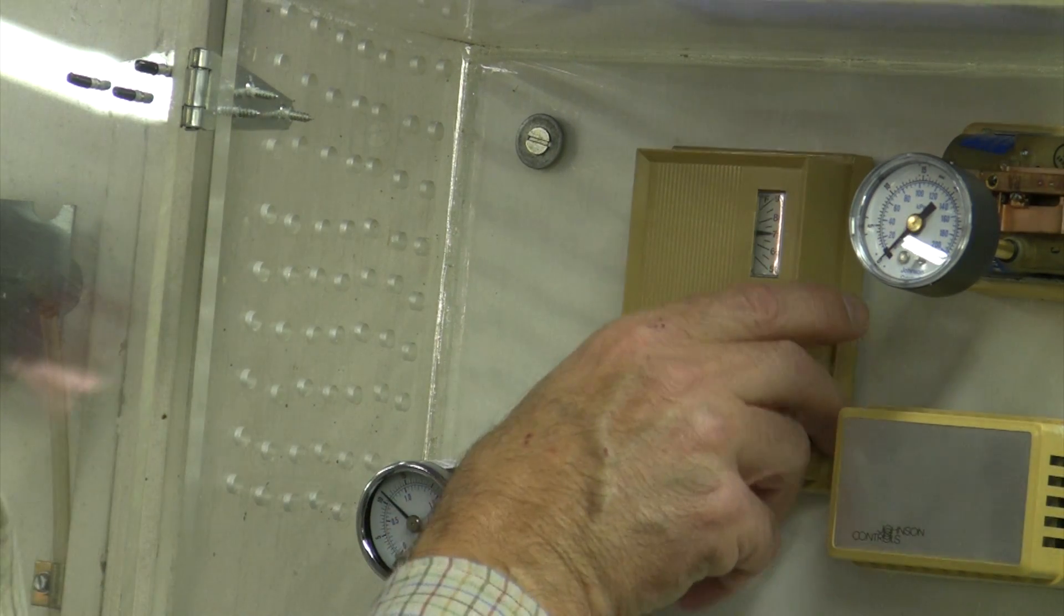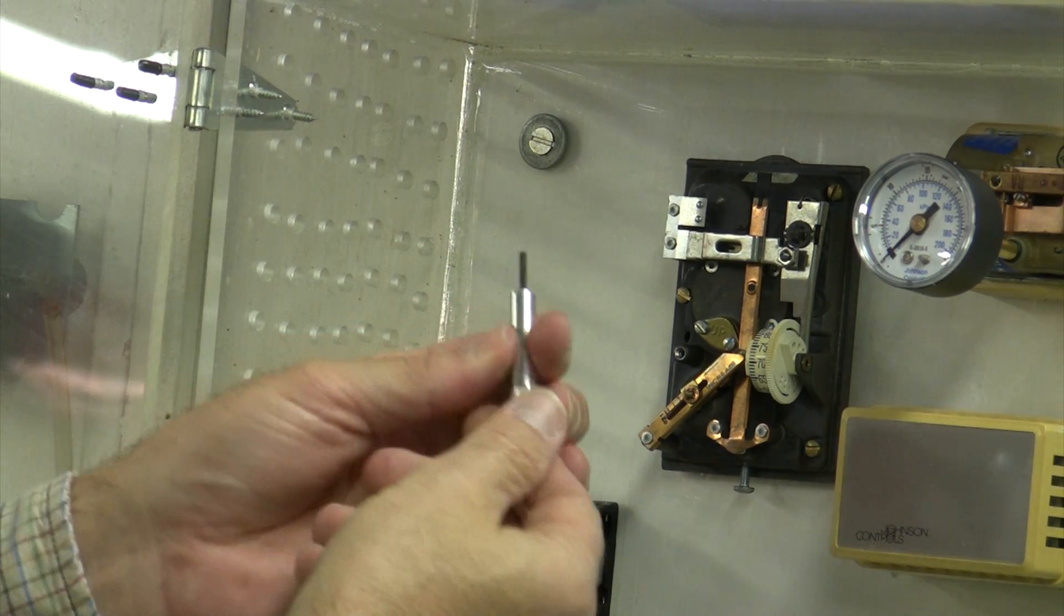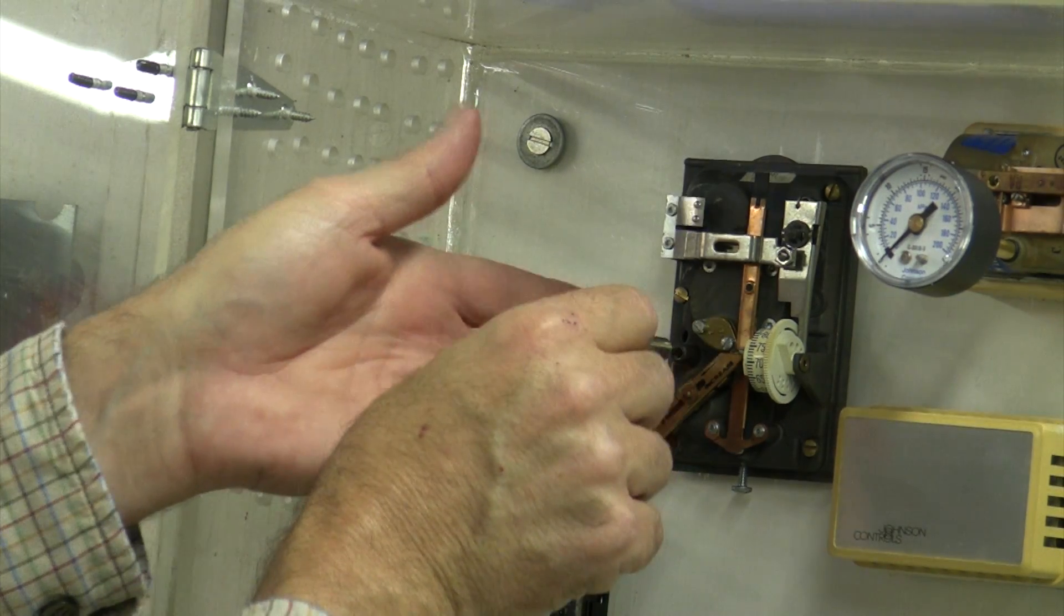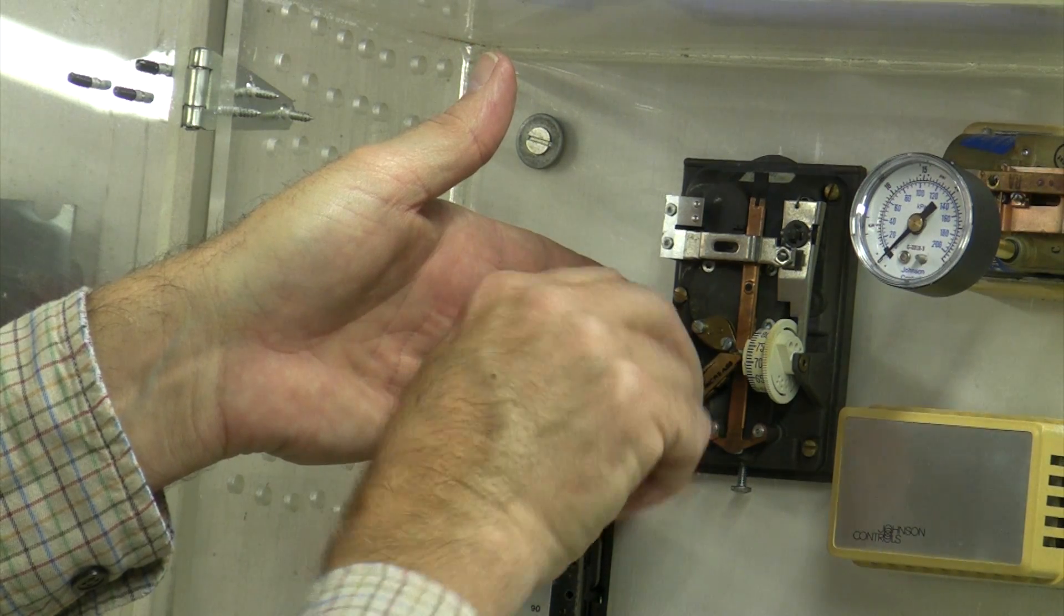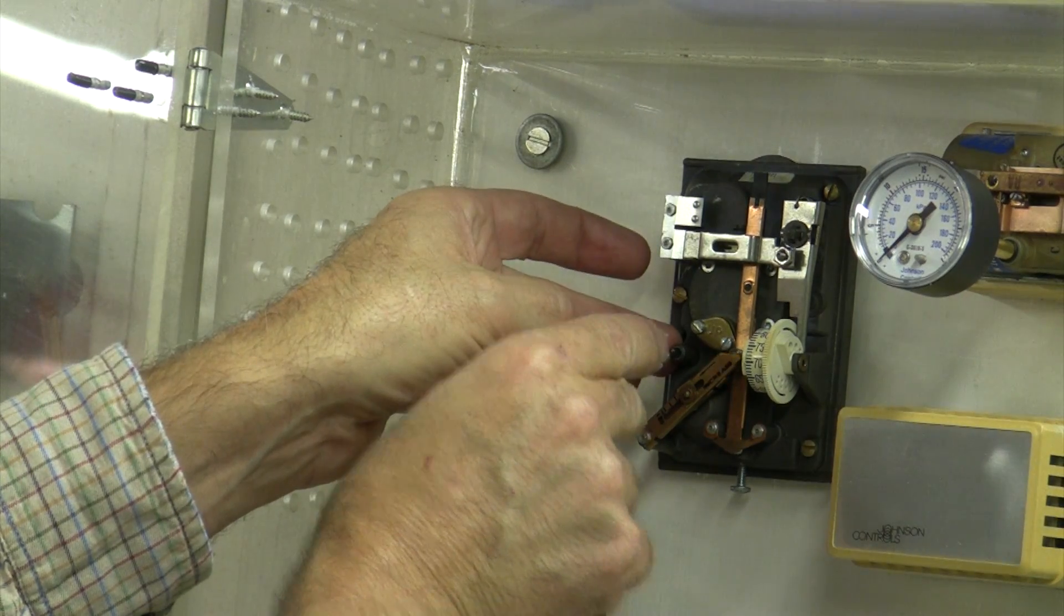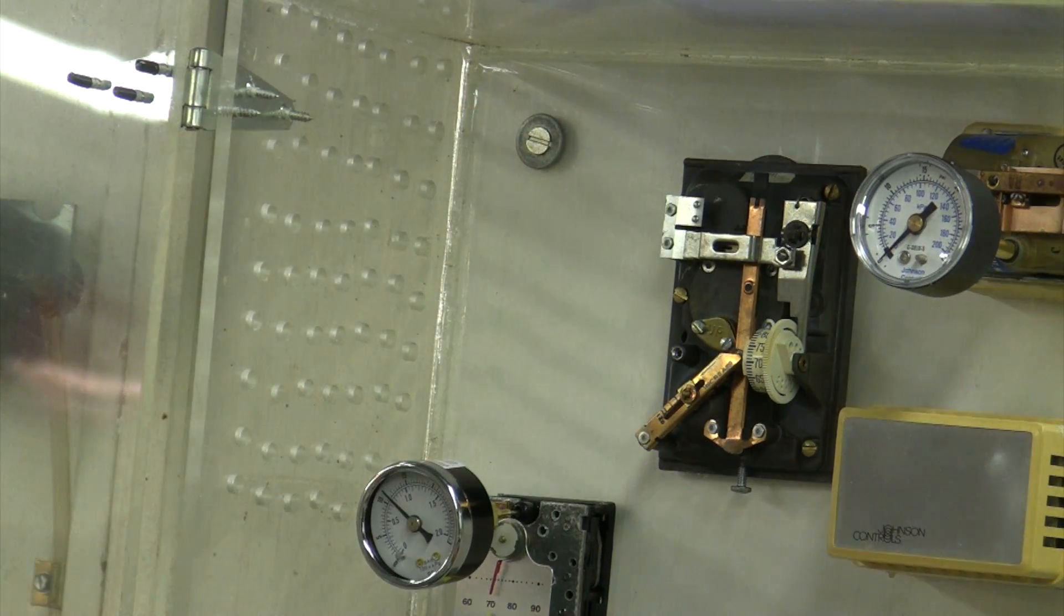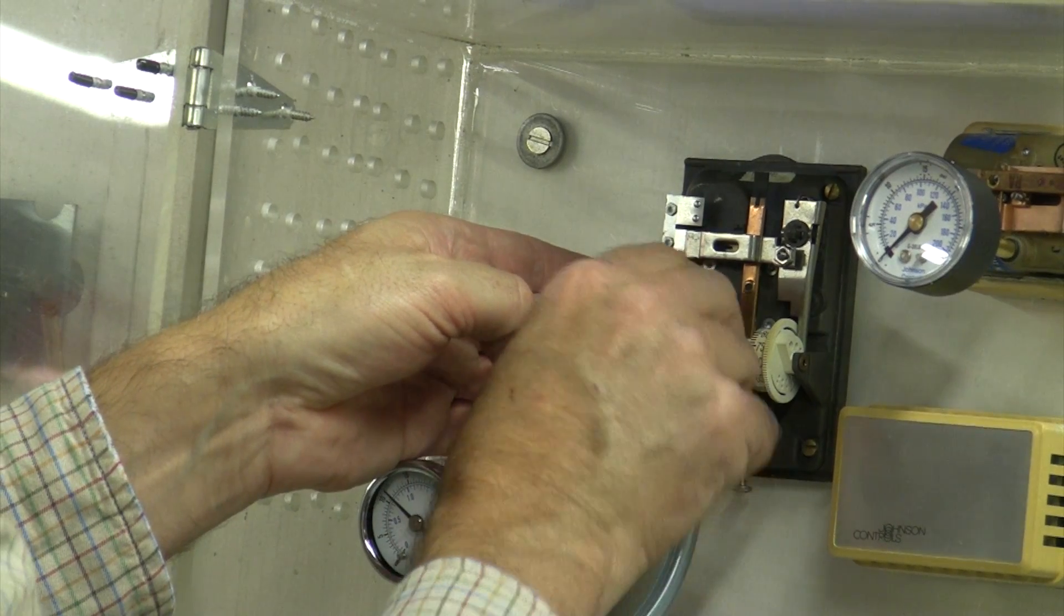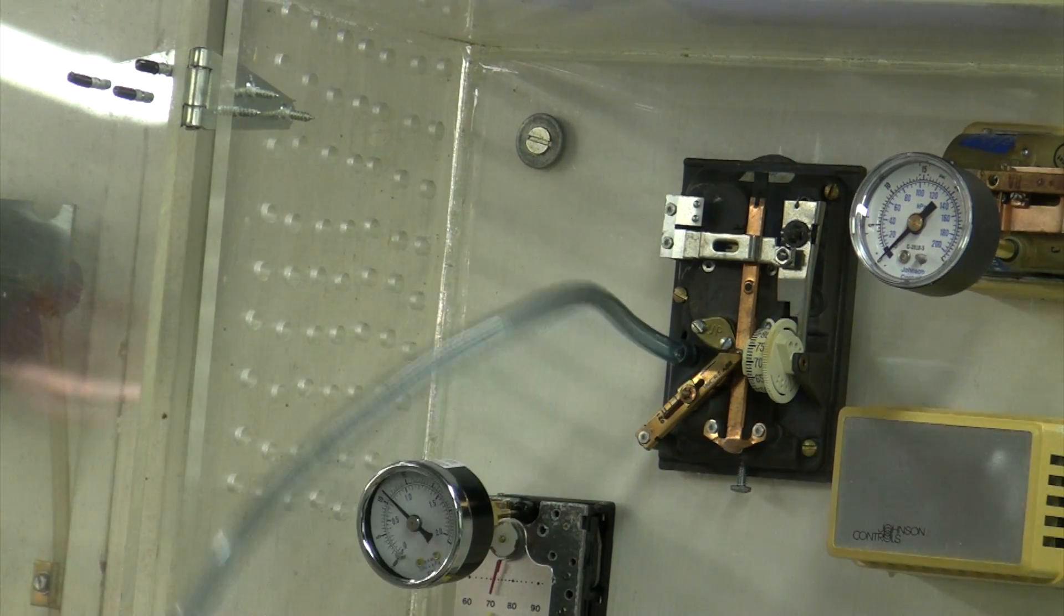Moving to the Barber-Colman. I've got a tool for the Barber-Colman. On one end, if you go right to the left middle part, there's a little Allen screw that you just give a little counter-clockwise turn, and it'll bleed a little bit of your calibration pressure off. Now we take some flexible tubing, and I'm going to slip it over that housing where that Allen screw resides.